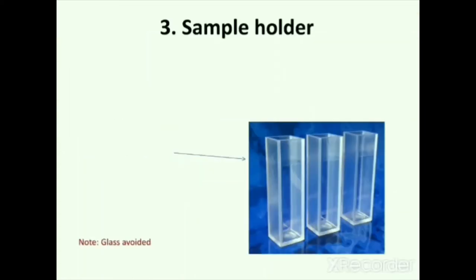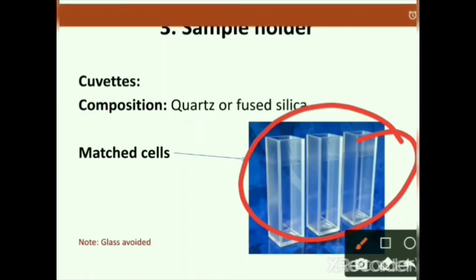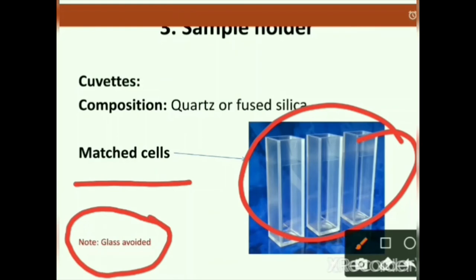The sample holder uses cuvettes made of quartz or fused silica. In the spectrophotometer, matched cells are used — these are cells of exactly the same composition. Glass is avoided in cuvettes because it absorbs electromagnetic radiation.